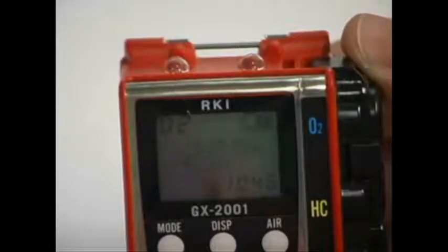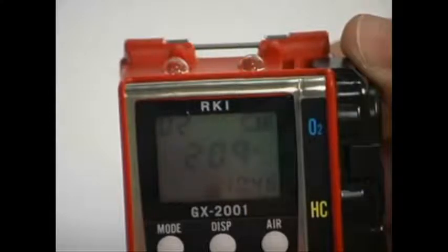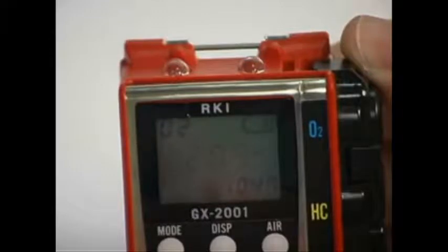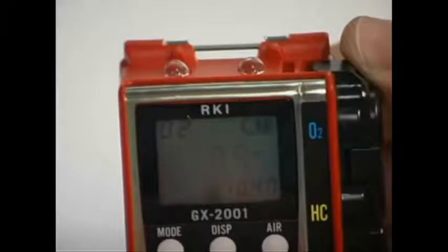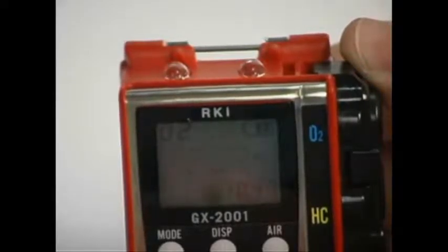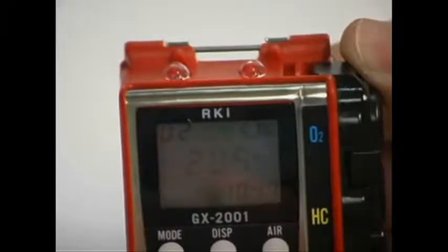The GX-2001 also sounds an alarm and vibrates when the second alarm point is reached for hydrocarbons, CO, and H2S, or when the concentration of oxygen rises above 23.5%. The flashing LED lights, audible tones, and vibrations of alarm 2 will alert at a rate of twice per second. The LCD also displays the name of the gas in alarm, the backlight turns on, and the gas reading flashes. Other alarm conditions include TWA or STEL, overrange, low battery warning, dead battery alarm, and sensor failure.